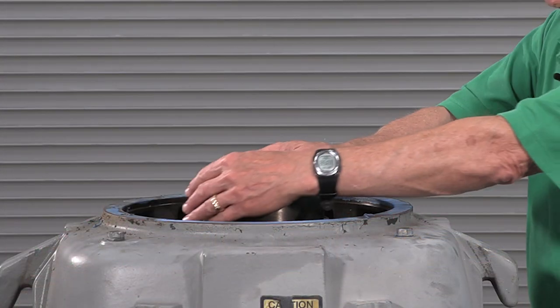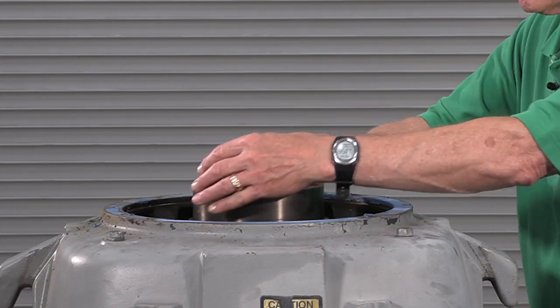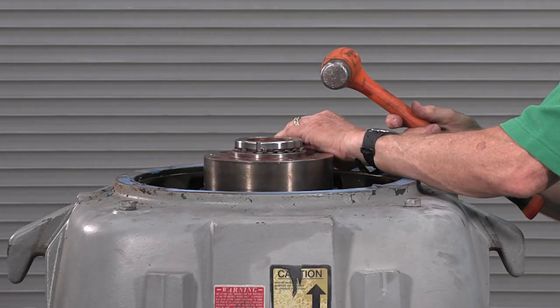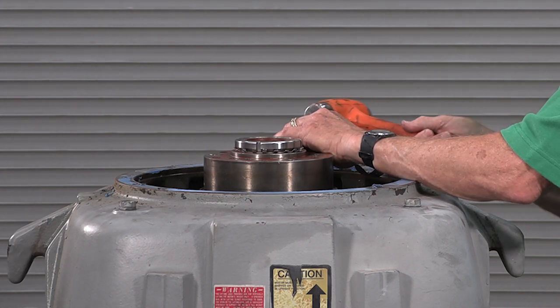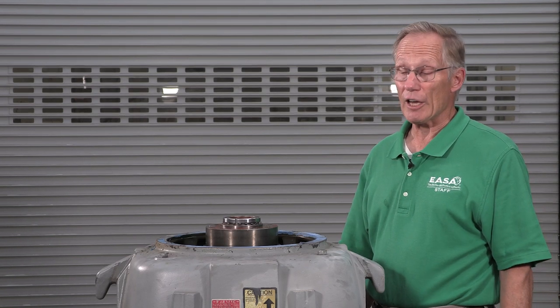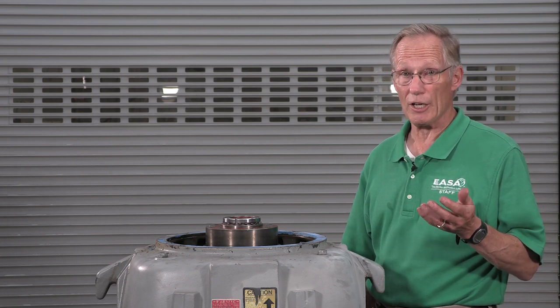Check to be sure the rotor turns freely — it does. So we'll lock the adjusting nut in place with the locking washer. This video covers the most common method of setting end play on a typical vertical pump motor. There are variations of this process, and some vertical pump motor bearing arrangements require special procedures, especially those with springs mounted under a spherical roller thrust bearing — but those are topics for other EASA videos.